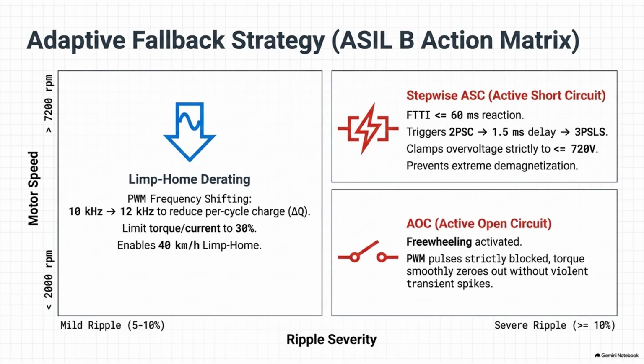But there's also a level 2 fatal error threshold. What triggers that? If the extraction circuit detects that the real-time ripple amplitude has spiked over 10% of the nominal bus voltage, so for instance, a 40-volt high-frequency ripple on a 400-volt system, and if it sustains that for just 20 milliseconds, the software declares an immediate critical emergency. 20 milliseconds is nothing.